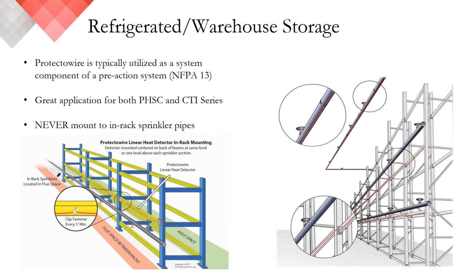However, in a manually operated and active storage facility, the in-rack sprinklers take an incredible amount of abuse. This is one area where we recommend keeping the detector off the sprinkler pipe and as far out of harm's way as possible. With this level of activity, it's not a matter of if, but when the detector will be compromised.